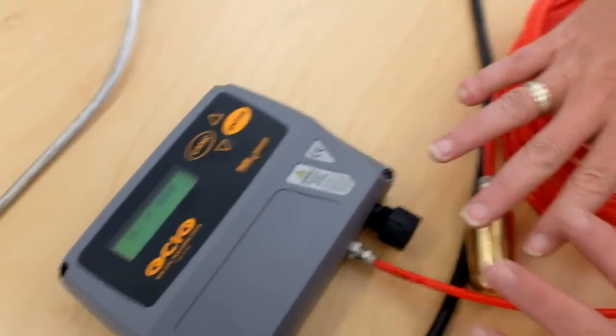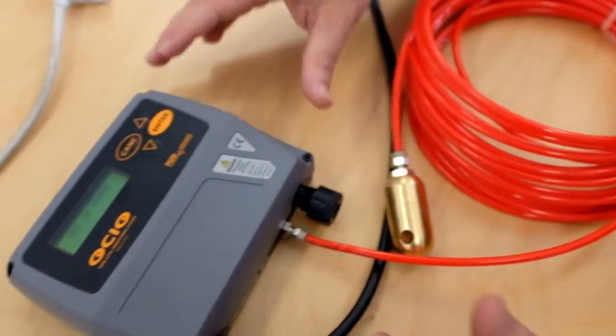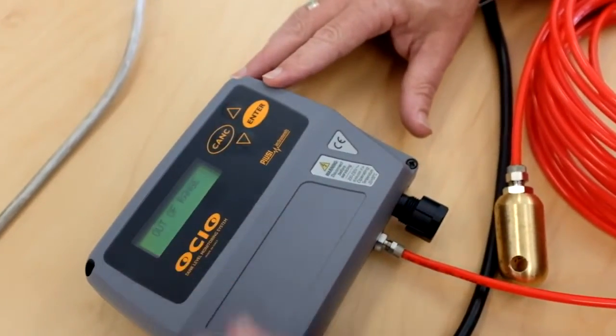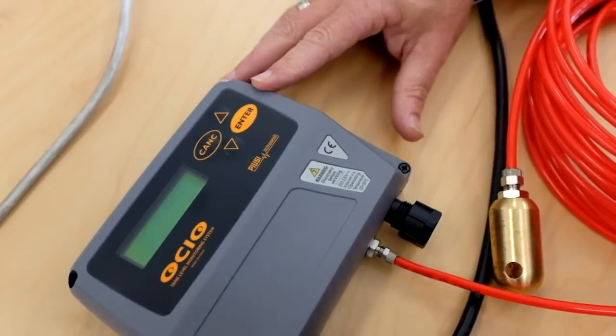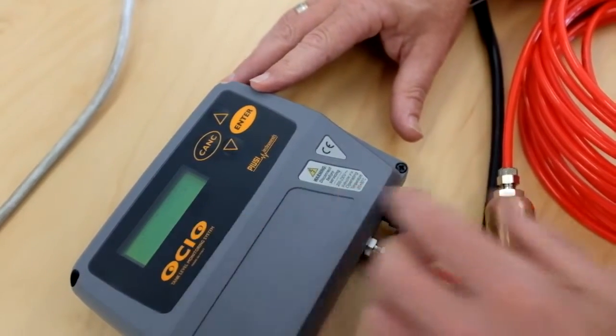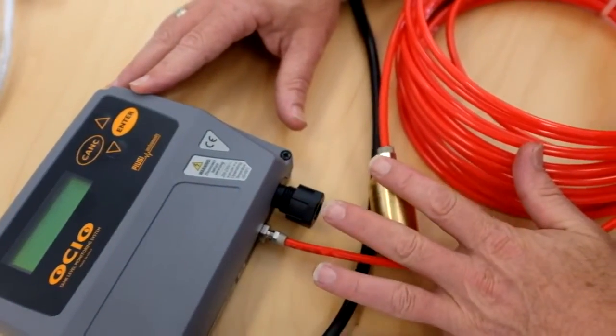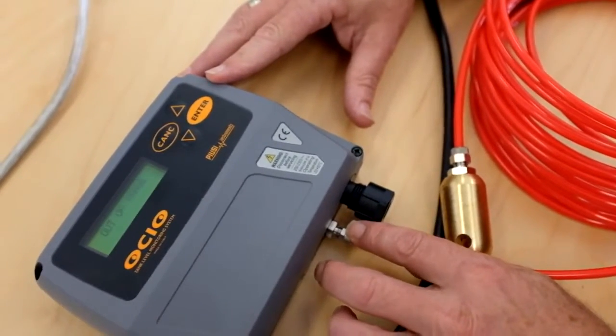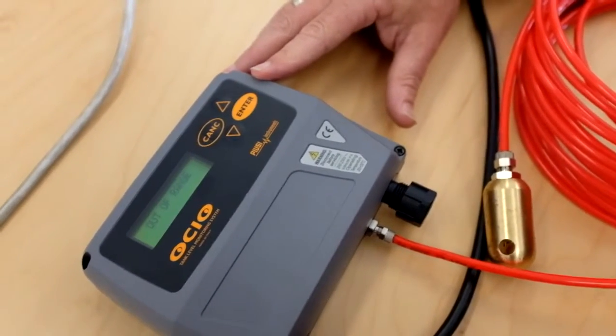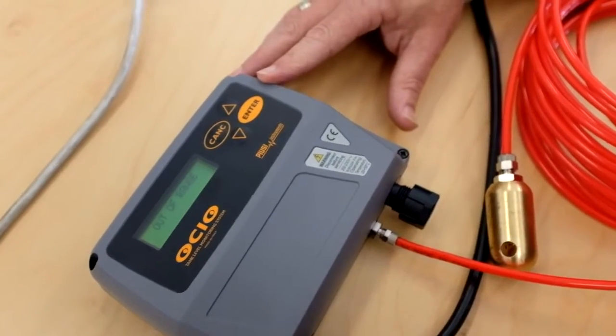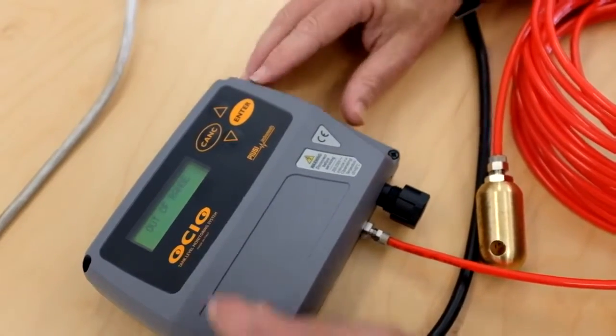At this stage, this thing is going through checking. Because it hasn't come back with an accurate reading, it's showing us out of range. If you get an out of range message and it's in the tank, it's been calibrated and set up, assume that there's something wrong with the air pump, okay? All right, we're gonna set this up from start. We're gonna assume this is brand new out of the box.